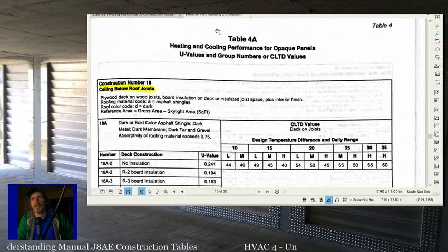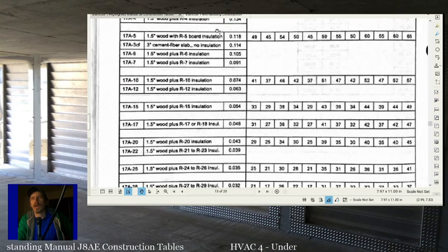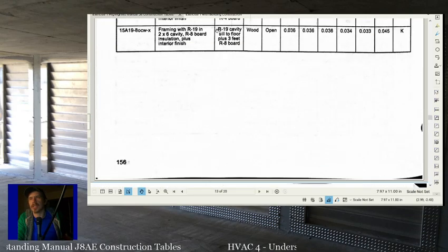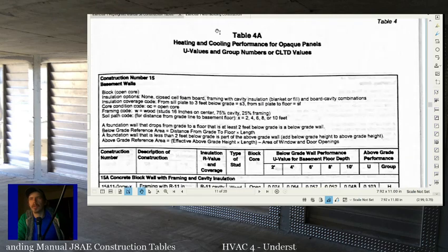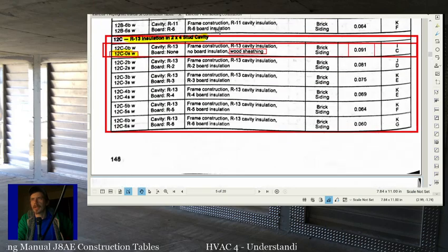It's not that easy. So what they do in Manual J is they basically do all the weird legwork for you on taking into account all those situations, so that they can just give you the HTM and you don't have to do all the complicated math behind it. So that's why cooling HTMs are different, because basically it's outside the scope of our job to be able to do the equations required to find the effective temperature difference in cooling. So they give us numbers to work with that are darn close enough. Okay, so that's why it's different. And if you read your book, it'll tell you about that.